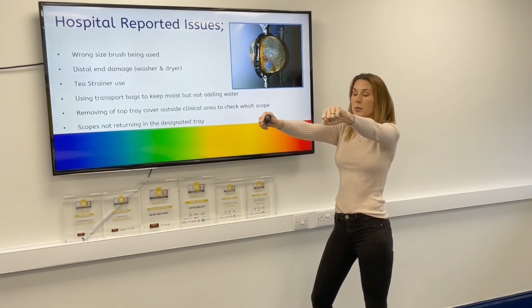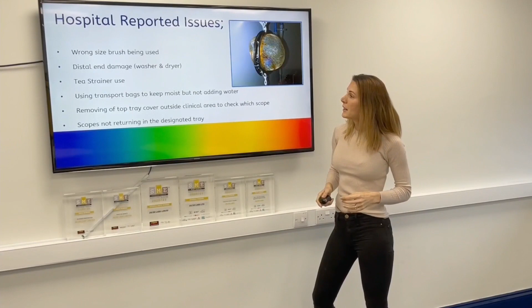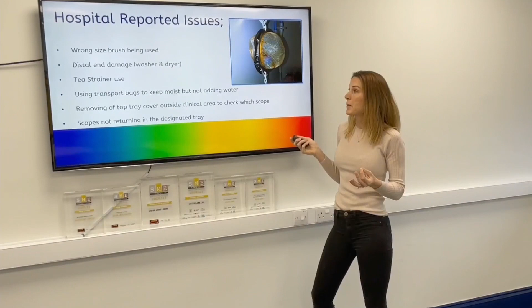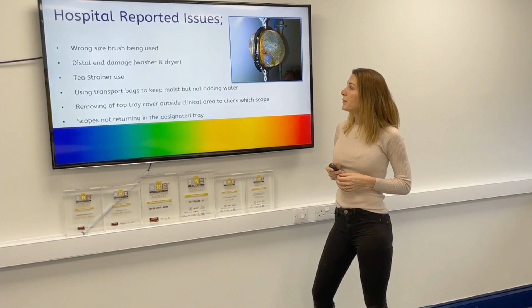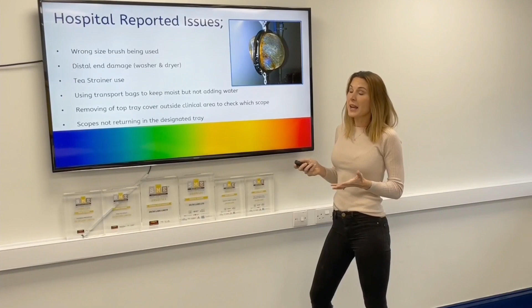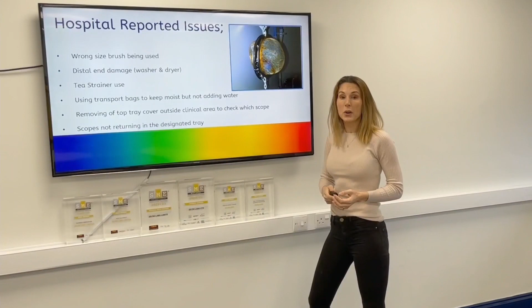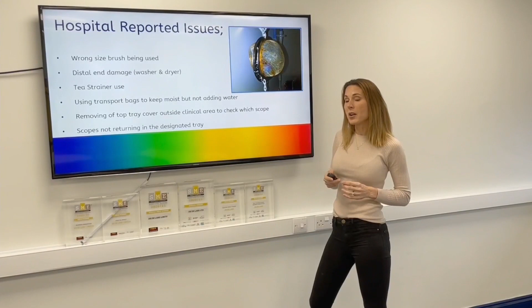Distal tip damage, very, very common, where they shove the tray into the washer disinfector, and the distal tips on the end smash, cracked. No one knows in endoscopy because they do not test electronically the endoscopes for damage before they go. So you end up with a patient ready to have their procedure, which they're probably already quite anxious about, and then them turning that endoscope on only to find out they can't do the procedure, which means that the patient then has to go away, they have to be called back. We've already got a lot of time delays, especially with COVID, and that could add 3 to 4 weeks before this patient then gets a diagnosis. And in terms of cancer, that's a long time.